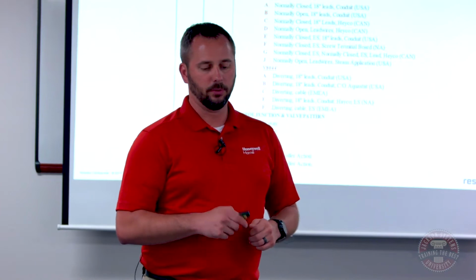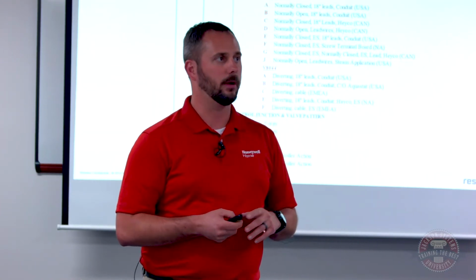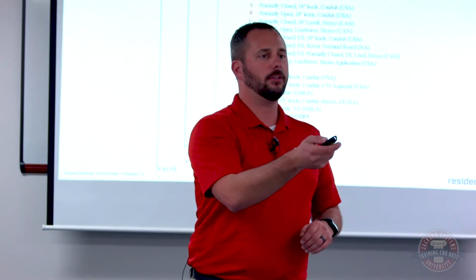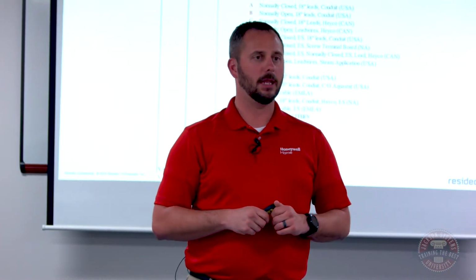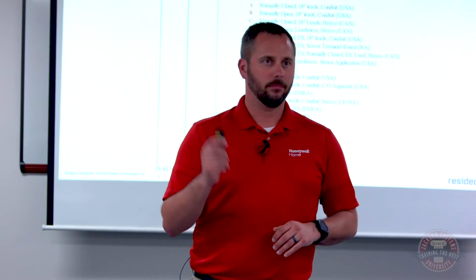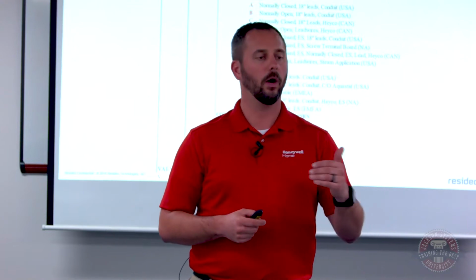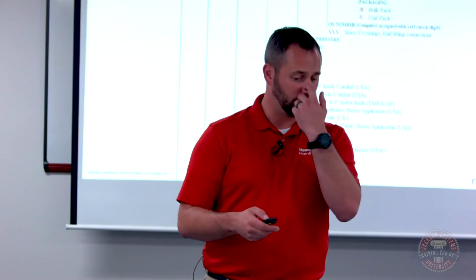And then I'm going to flow through this pretty quick. I had put a zone valve selection guide on here, but I'm running a little tight on time. I will make this available to Jackson Systems. We make many different types of zone valves, but probably 8 of them make up the lion's share of our business. This zone valve selection guide breaks down what all the numbers in a zone valve mean. So if you're looking at a V8043E1012, what does that valve mean? It means it's low voltage, two-way, it has 4 wires, it's 1000 series, and 3/4 inch. So it all breaks it down. I have 2 different slides because there are a lot of them.